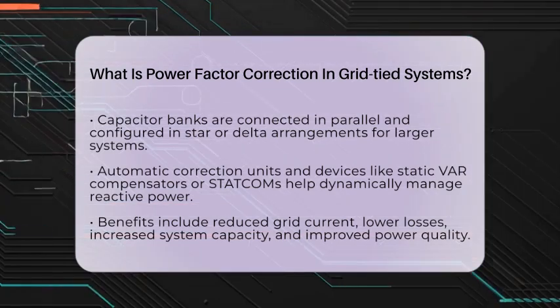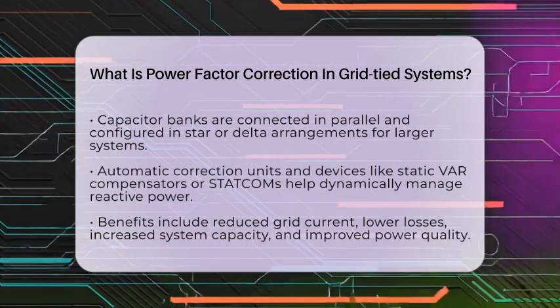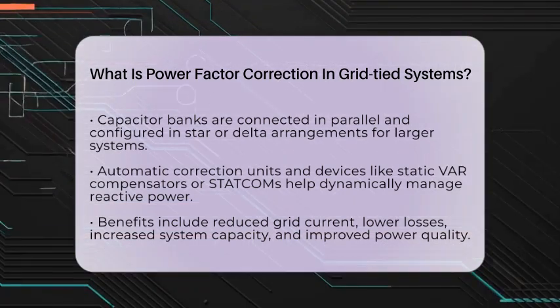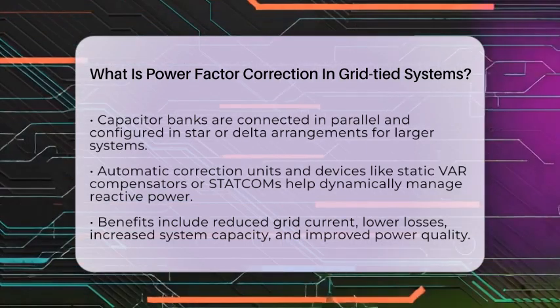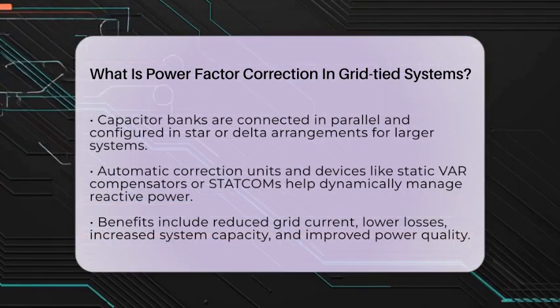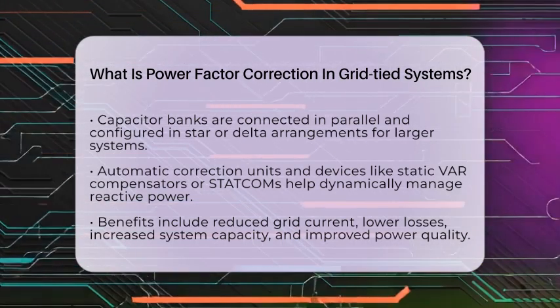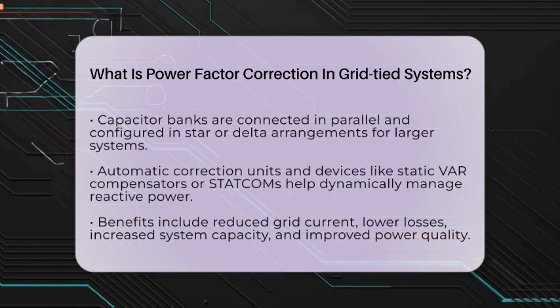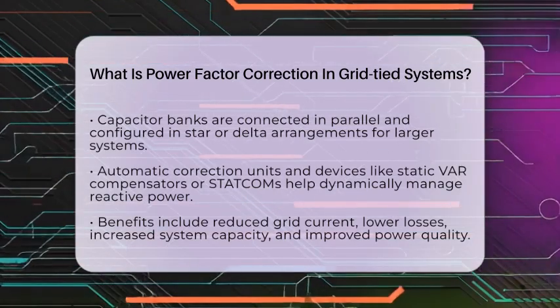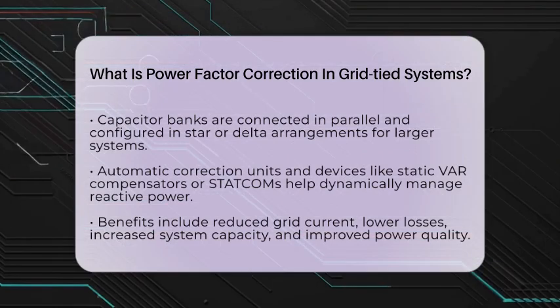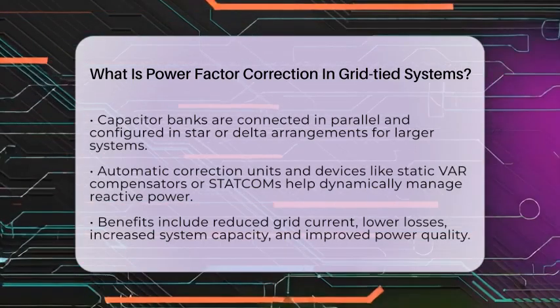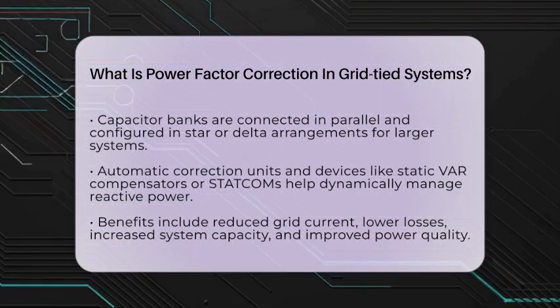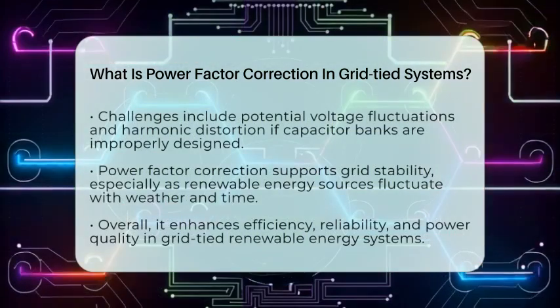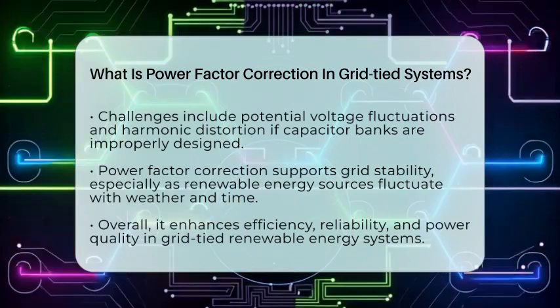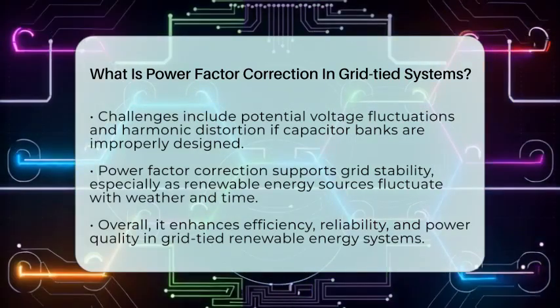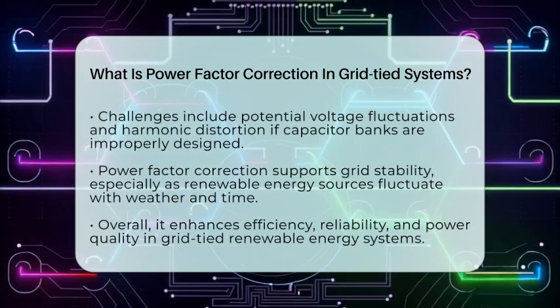The benefits of power factor correction in renewable energy systems are significant. It reduces the amount of current drawn from the grid, which lowers losses and improves overall efficiency. It also increases the capacity of the system by freeing up apparent power, allowing more energy to be generated or consumed without upgrading infrastructure. Better power quality and voltage stability are additional advantages, helping to prevent equipment damage and reduce utility costs. However, there are some challenges.